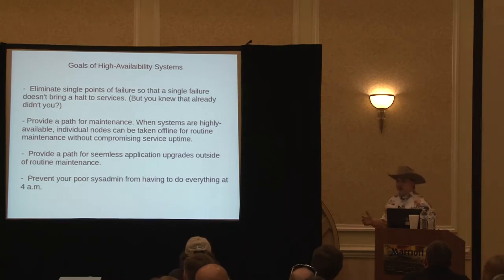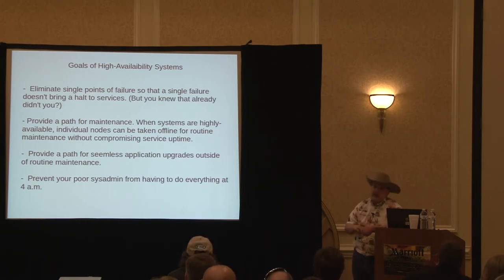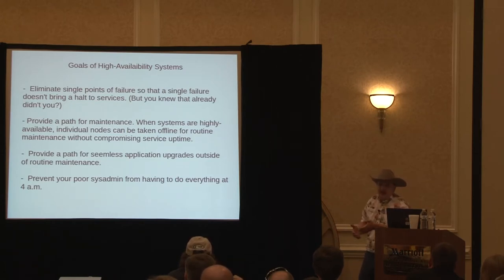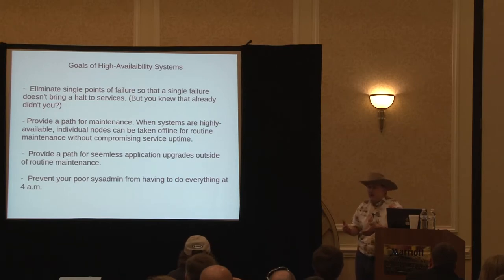When designing high availability systems, the first thing you have to do is start eliminating single points of failure. A lot of people look at their boxes and think, 'I've got RAID, I've got redundant power supplies.' Those are great — they're our first line of defense. But if you actually need stuff to stay up all the time, you have to look beyond that. It doesn't do you any good to have redundant power supplies plugged into the same power feed, like a UPS. If that thing fails, your server does too.